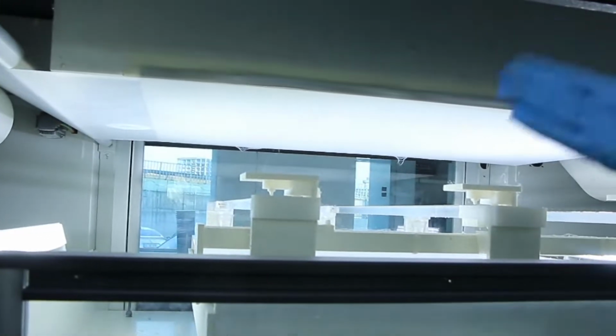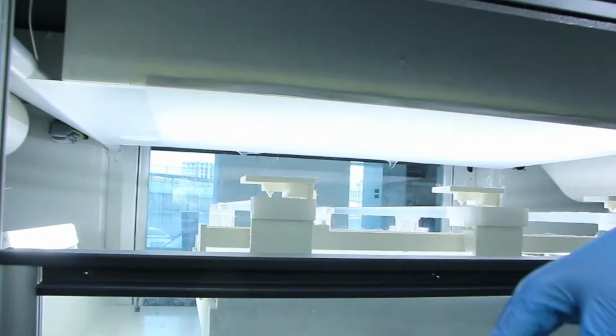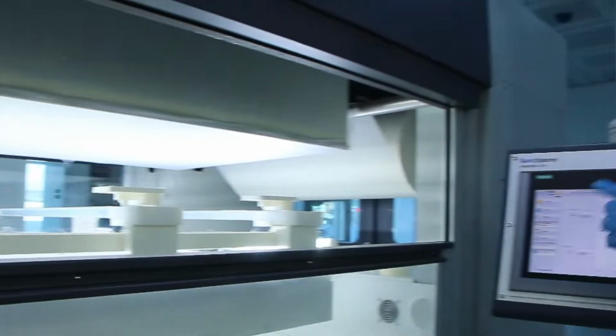I think if you notice that when I activated the atmosphere settings, you don't want to open the chamber by any means. So you can also set it to a mode where if the door ever opens, the process will rather come to a halt. So I'm going to open this with the dehumidifier on. Now you might notice, okay, I have a dehumidifier on, but just opening the door to the external ambience room will affect the value. And then you get your error right here, indicating that please close the doors.